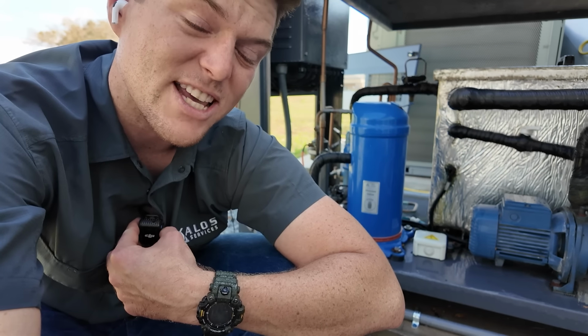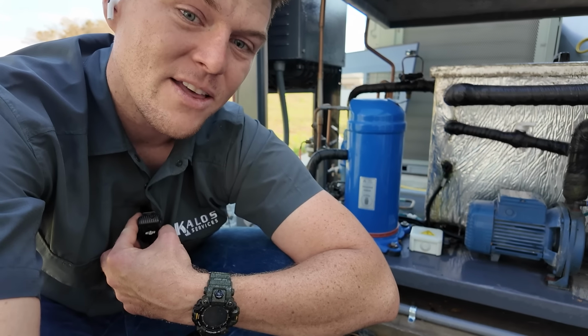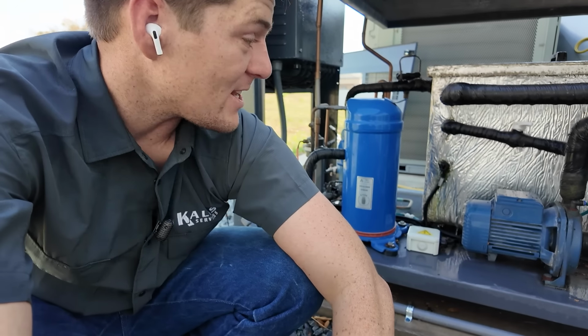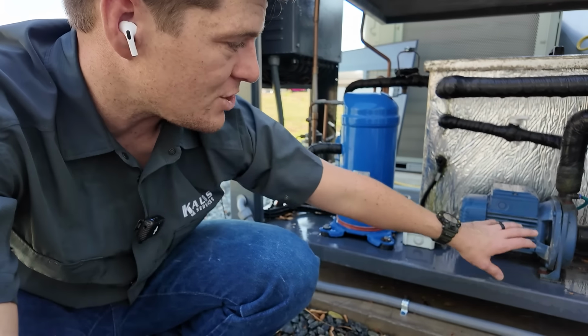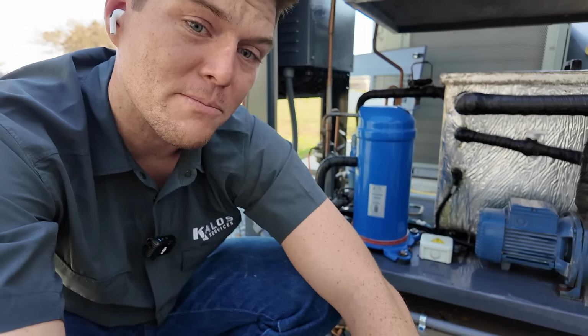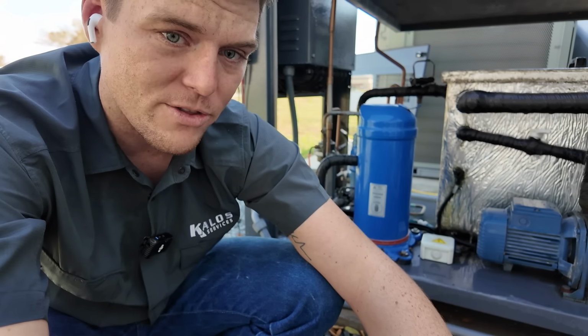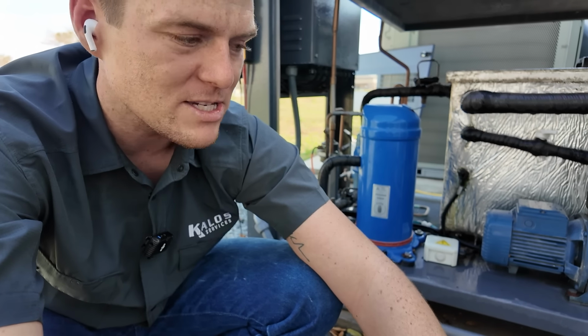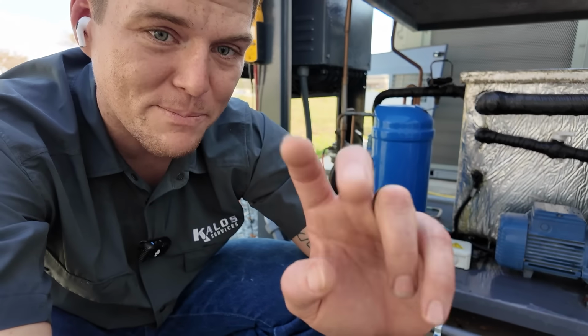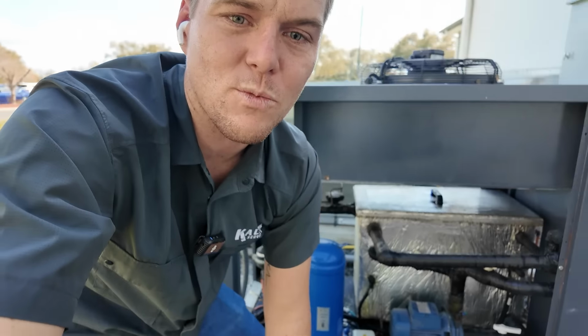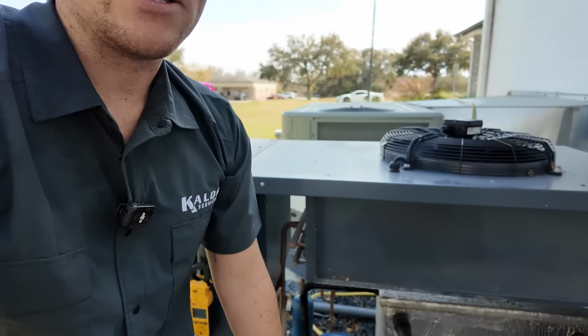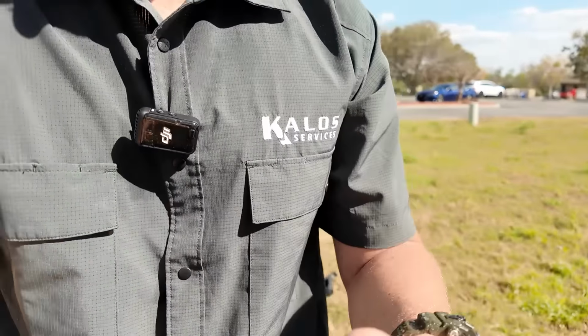So who knows what kind of sediments built up inside this pump over time. They've come back to. Now, that's not the biggest problem. After I was able to change the programming of the amp draws that it looks for the motor, to then ignore the motor that might be failing with bearings that I can get replaced, the second issue that popped up is the condenser fan motor didn't want to come on anymore.